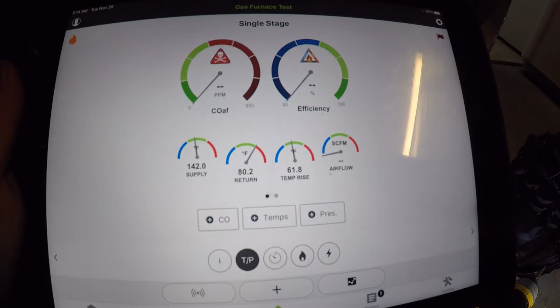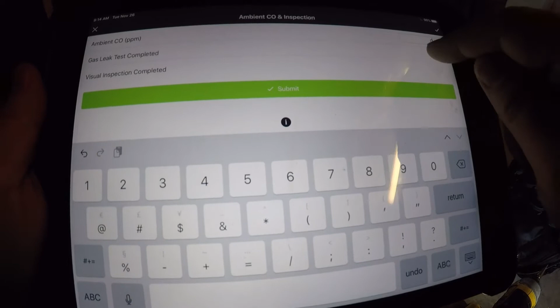So if I look here, temperatures, supply, everything's good. Picking up no CO, no gas leaks, visual inspection done. I'm going to capture my temperatures and I'm going to get ready for my combustion test. Loosen my test port, which I did. My analyzer's zeroing. Getting ready for combustion.